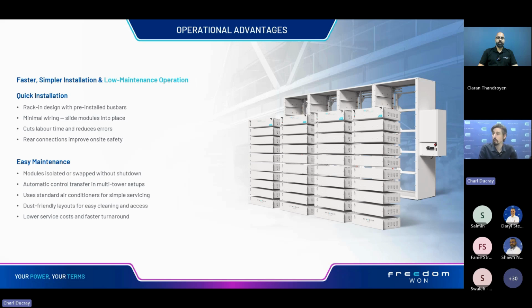We also have pre-installed bus bars. Could you tell us a little bit more about that, Karen? That's slightly different to what we've seen out in the field. Yeah, so we found that the pre-installed bus bars make site installation much quicker. The top modules attach to vertical bus bars, which allow all the modules to be parallel on the single tower. Then there are horizontal bus bars which connect all the top modules to each other, which then parallel all those towers. This is a much quicker and safer method than performing all of this on site.